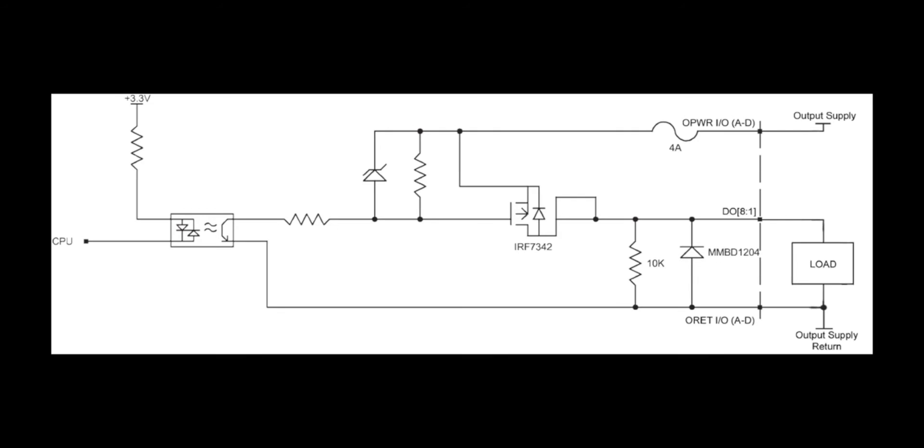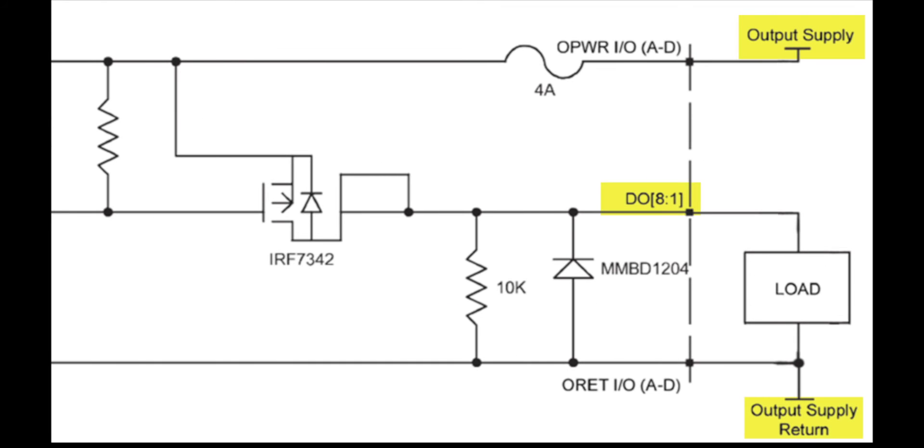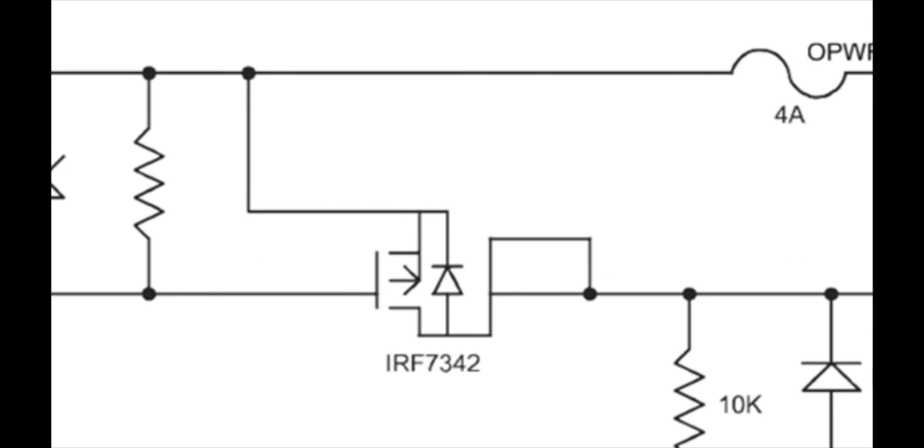The 500mA option also has its own unique properties. Although much more complicated internally, the sinking and sourcing options are wired in the same way as the sinking and sourcing options previously shown. One of the differences is that the switch type is an opto-isolator and a MOSFET. When off, the MOSFET acts as an open circuit.